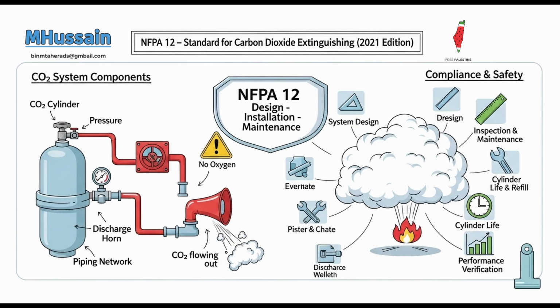When I hear that, my mind immediately jumps to a completely sealed room being entirely filled with gas. Is that a pretty accurate mental image? That's precisely the concept. A total flooding system is designed to discharge carbon dioxide into and completely fill an enclosed space or an enclosure built around a specific hazard. Fill the whole box, to achieve a precise extinguishing concentration throughout the entire volume. This means the space needs to be reasonably well enclosed to minimize agent loss. Yeah, keep the gas in.